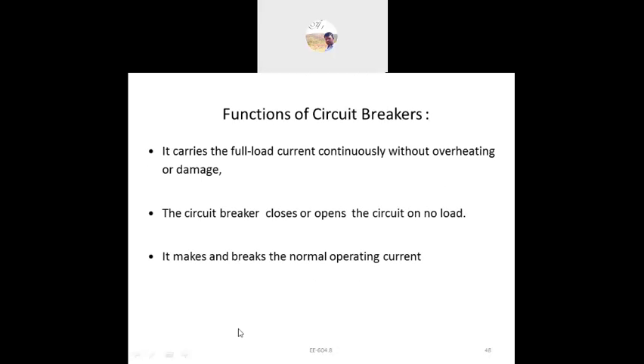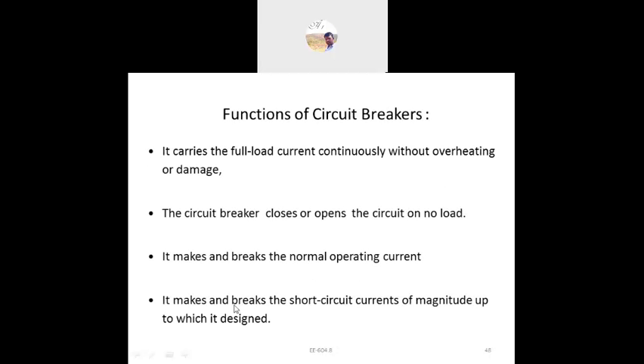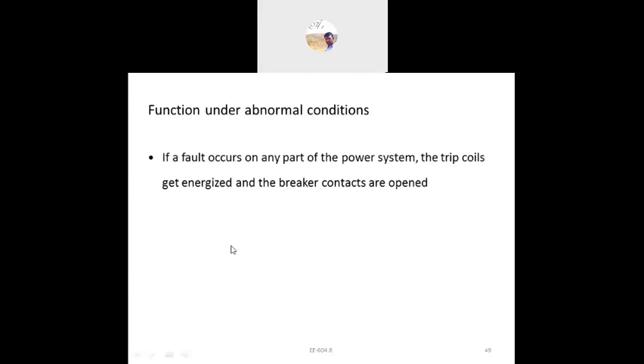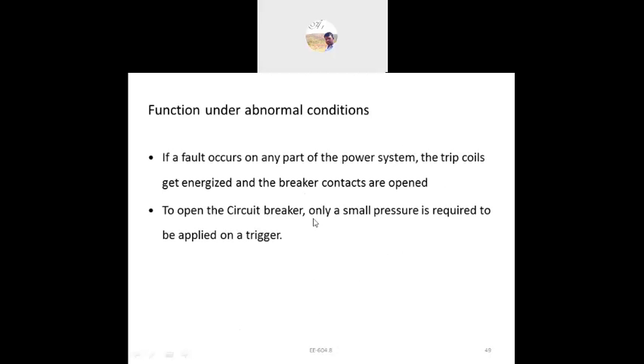It makes and breaks the normal operating current. It also makes and breaks the short circuit current. Under abnormal conditions, that is when a fault current flows, when the fault occurs in any part of the power system, the trip coil is energized and the circuit breaker contacts open. Only a small pressure is required to open the circuit breaker, which is triggered by the signal given to the relay coil.